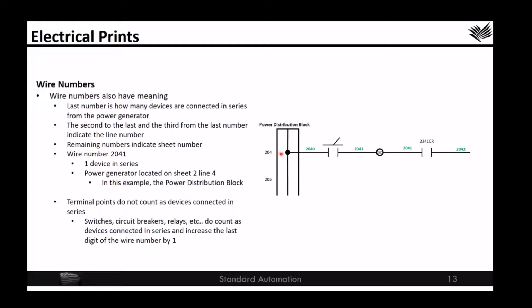The second to the last number and the third from the last number indicate line numbers. So an 04 indicates that it is on line 4. Followed by a 0 means that there are no devices connected in serial. Followed by a 1 means that there's one device connected in serial. And then followed by a 2, and so on and so forth. The remaining numbers indicate the sheet number.